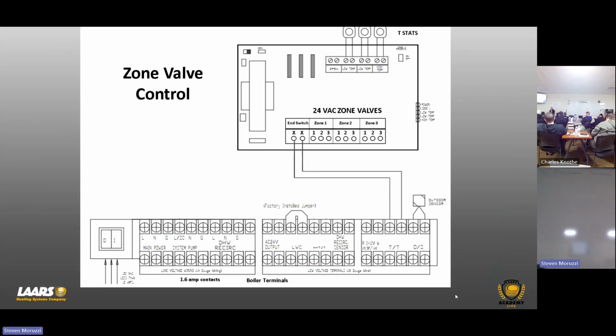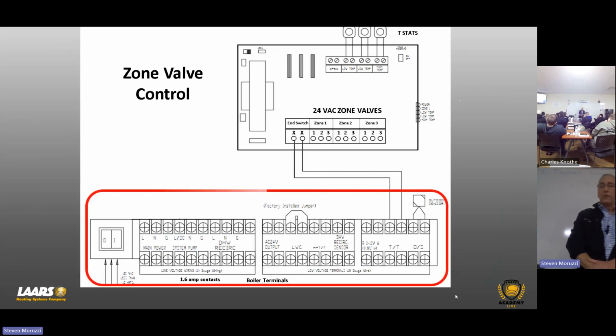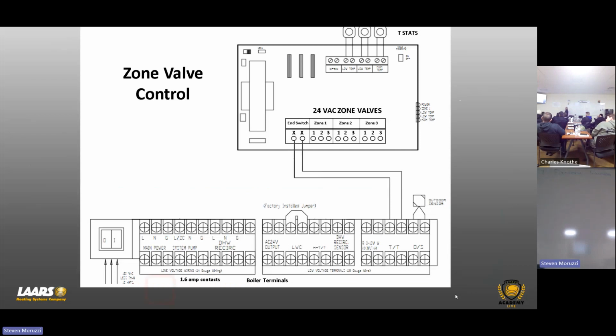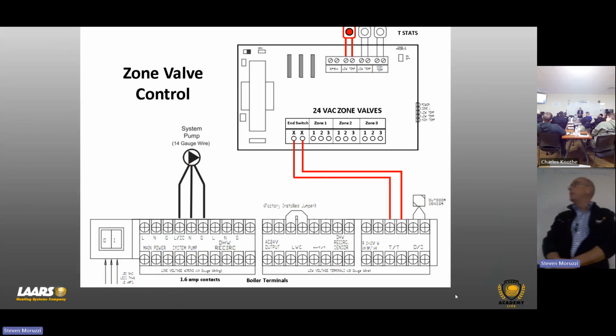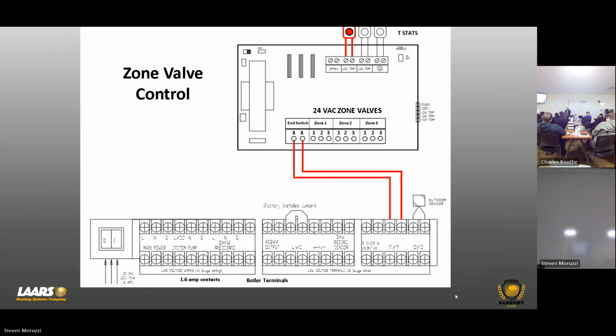So what I'm showing here is zone valves. Okay. So example, Caleffi or Tekmar. And down here is our terminal strip for the boiler, and then whatever zone panel you're using. In this example, I've got a TT demand, and we are going to close XX, which tells the boiler we have a demand. Now we have to fire or energize the pump. So we energize the pump, the system pump. And I talked about modulation here if I've got a combi boiler. So if I hit 80% of modulation, I need to make sure I've got enough BTUs for my domestic demand. What we will do is we'll drop out that system pump. And as I now catch up and I start modulating back down to 50%, we reintroduce the pump. Okay. So that's how we're doing that.